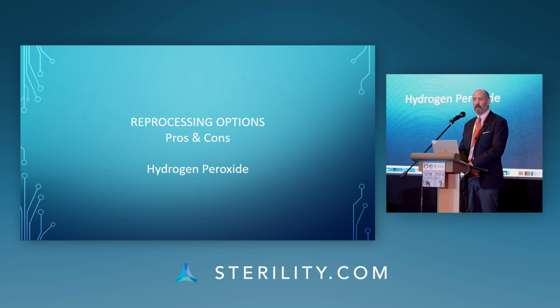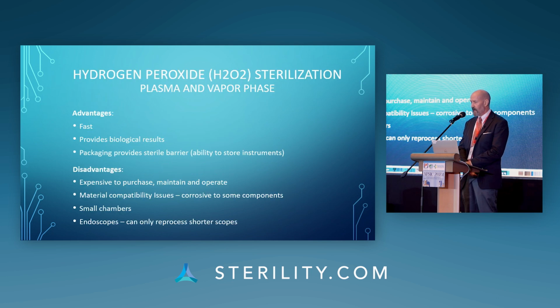Next, I'd like to talk about hydrogen peroxide sterilization. Hydrogen peroxide is true sterilization. It is fast. It provides biological results, which high-level disinfection does not. And very significantly, it affords the use of terminal packaging, so that you can package a scope and it remains sterile when you've removed it from the sterilizer, and it's sterile until that scope is used.